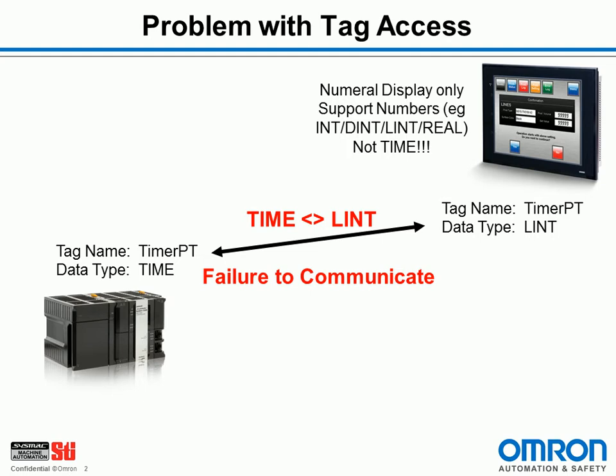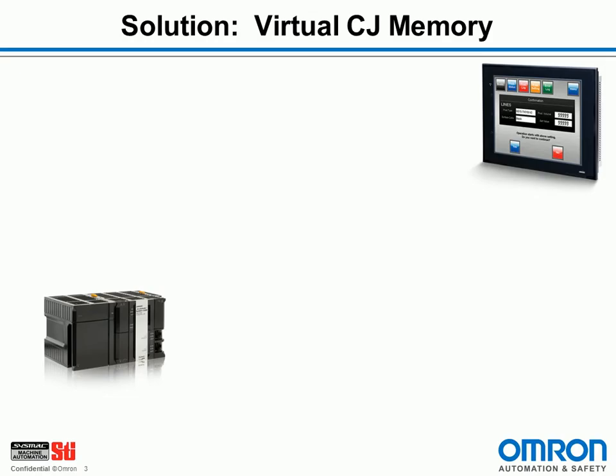So how can we solve this? We can take advantage of the virtual CJ memory. So each NJ has all the memory areas in it that a CJ PLC would have. That's to support legacy communications.